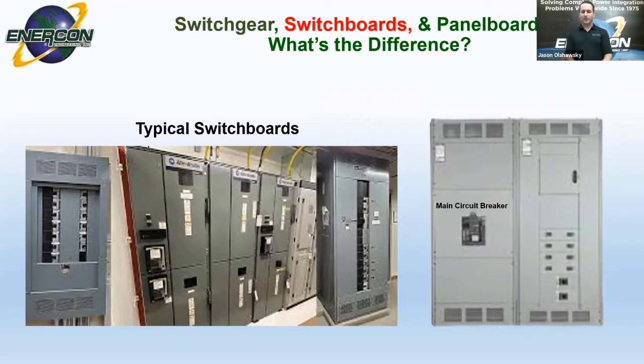And then through that breaker would feed typically copper bus over to the distribution. Some of the switchboards there on the left side may just have cabling directly to that bus. So to isolate that would be from the switchgear. With the main breaker, you get that local isolation capability.